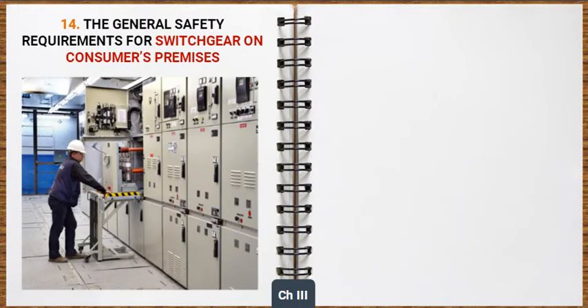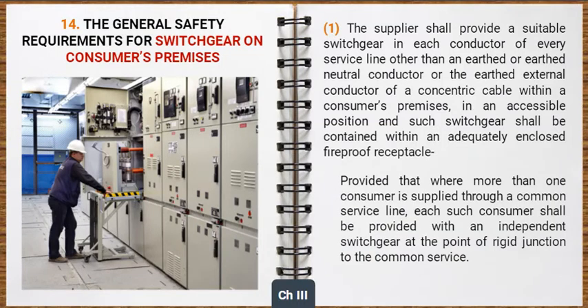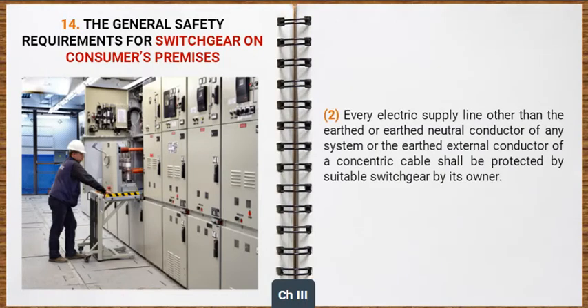Now let's learn about the general safety requirements for switchgear on consumer premises. The supplier shall provide a suitable switchgear in each conductor of every service line, other than an earthed or earthed neutral conductor or the earthed external conductor of a concentric cable, within a consumer's premises in an accessible position. Such switchgear shall be contained within an adequately enclosed fireproof receptacle. Where more than one consumer is supplied through a common service line, each such consumer shall be provided with an independent switchgear at the point of rigid junction to the common service. Every electric supply line, other than the earthed or earthed neutral conductor, shall be protected by suitable switchgear by its owner.